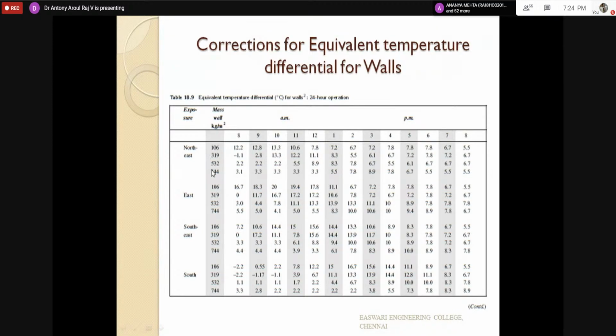Suppose the mass is higher, like 744. Then it will shift the peak to 4 o'clock or even 8 o'clock, if the size and capacity of the building are more. So we have lightweight, medium weight, and heavyweight construction. For heavyweight constructions, the shift will be much higher and the peak will be reduced, which is the advantage. We don't want the temperature to enter the building through the wall, so we go for massive construction, or reduce the size and increase the heat capacity of the material. That's what we need to understand.